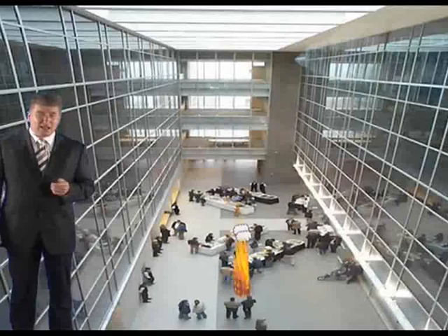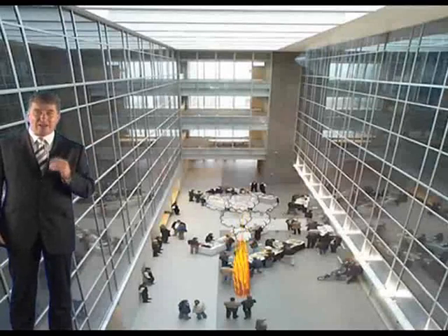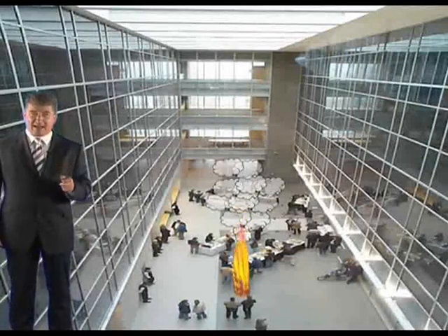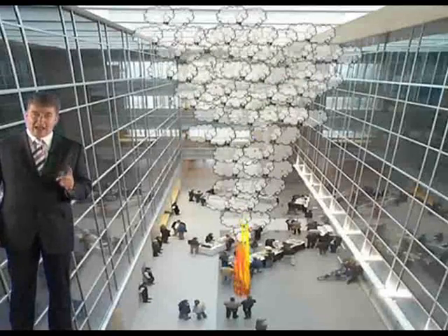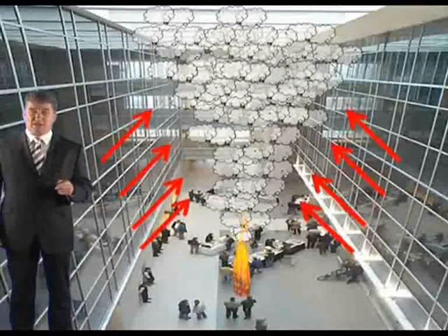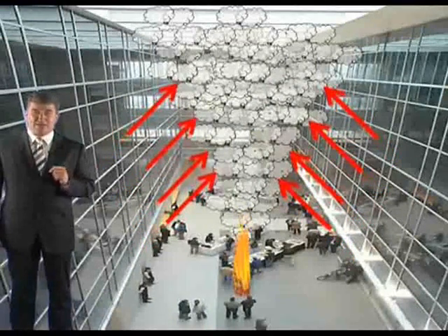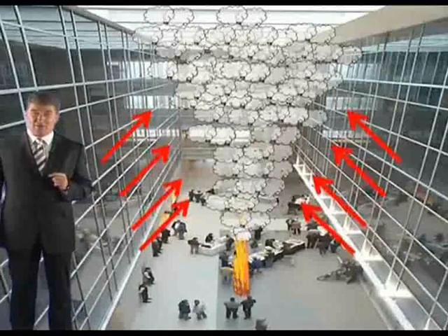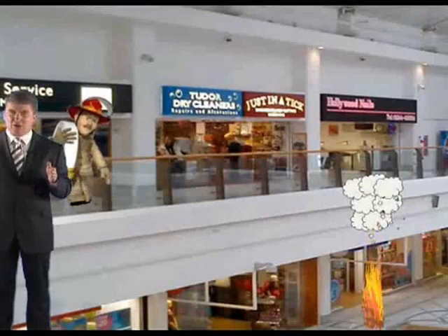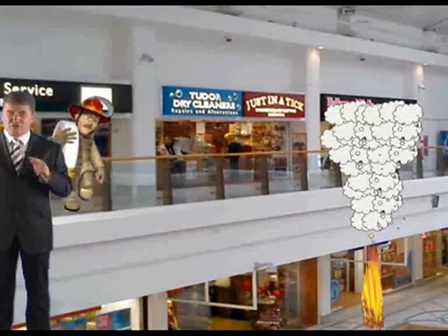Fire development. It's essential that you understand the principles of fire development, on how a fire grows and spreads through a building. You need to understand these principles to enable you to determine the ventilation requirements. Now, the fire produces hot gases which rise above the fire, forming a plume. As this plume rises, it entrains cold air, and this increases its mass flow rate and the diameter of the plume. Now we're going to look at the smoke layer that descends at a known rate later.